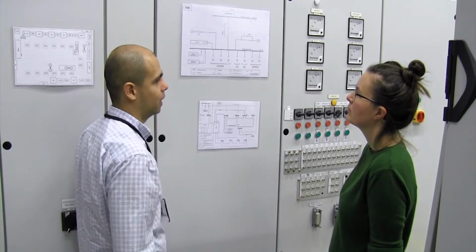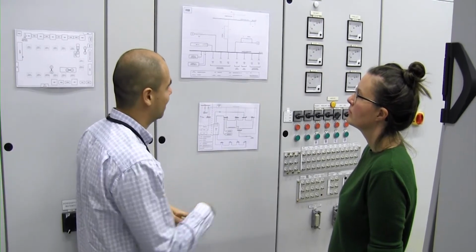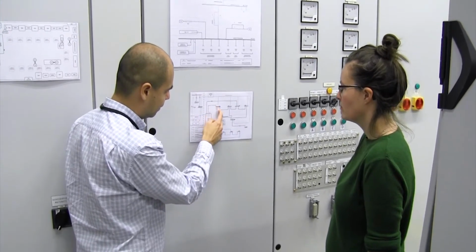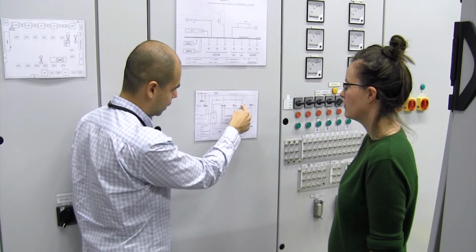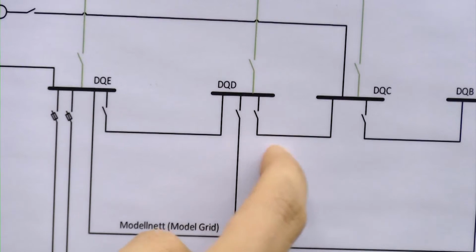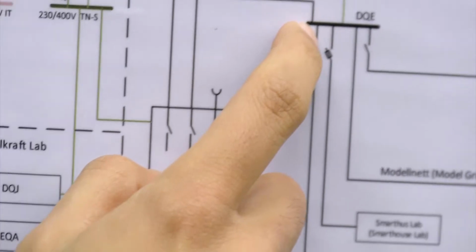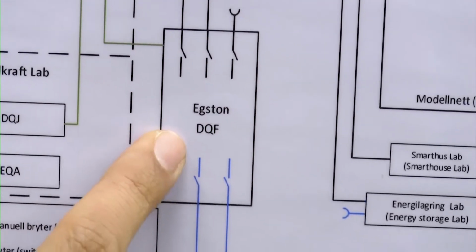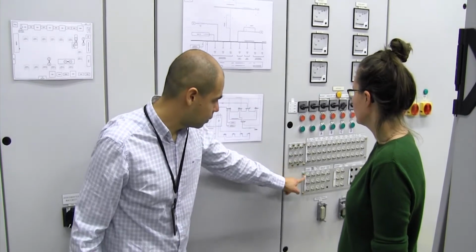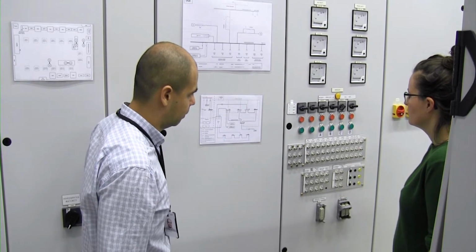The other side is where we have our digital substation, a small digital substation in the lab, and this is where we are bringing some of the things. You can see here how we can go until the device where we have the devices connected. If we have a device in the C bus, we will connect something at the C bus, and then we just come until here, sending the voltage with our power supply. It is a big control supply. Also, we can check some of the voltages at the node with the multiple measurement equipment.